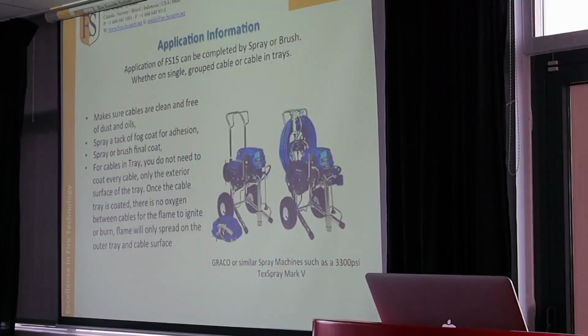So for cables in trays, you do not need to coat every cable, only the exterior surface of the tray. Once the tray is coated, there's no oxygen between the cables for the flame to ignite internally or burn. So flame will only spread on the outer surface of the tray and or the cable. Then having the cable coating there, which is zero flame spread, means that the flame will simply not spread at all.